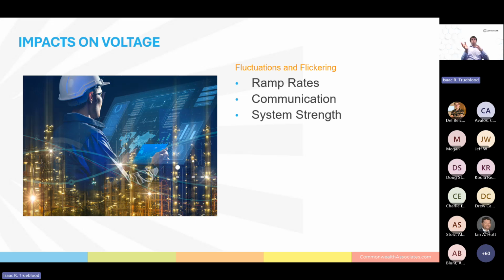Lastly, a mitigation option, while effective, I will admit is less practical. By increasing the strength of a distribution system, the difference in voltages between the beginning and end of a feeder is greatly reduced, allowing for easier voltage sensing and regulation. However, this will require drastic measures, either increasing the distribution system's voltage or an increase to the power conductor sizing, neither of which is very practical or economical. However, I did want to include this option to cover that engineering wisdom of anything is possible. It will just cost a lot of money.